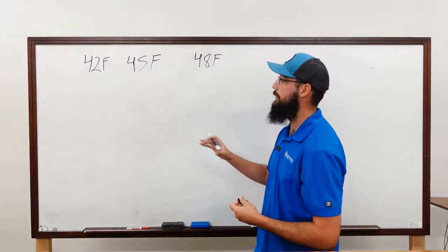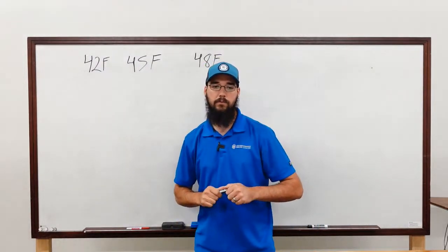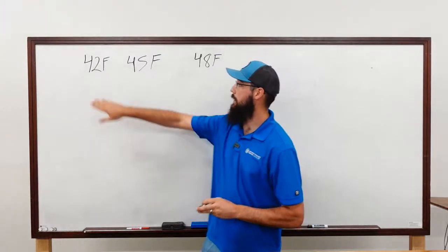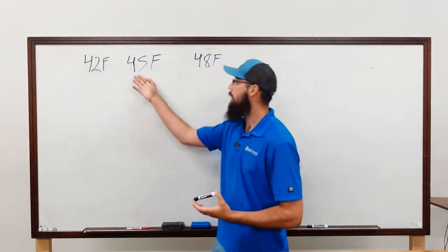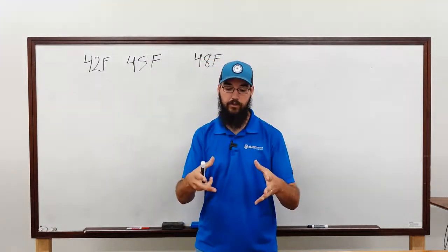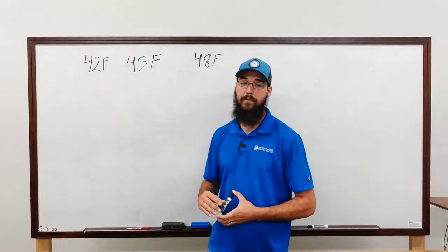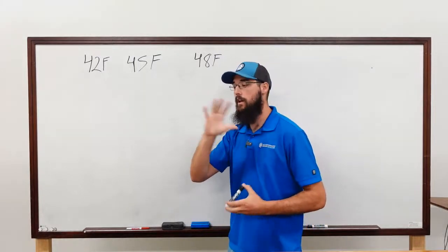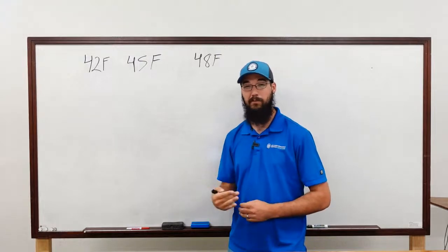And there's a lot of buildings, and I'm seeing this more and more. I'm not exactly sure why, to be honest, but for whatever reason, a lot of the engineering firms are speccing 42 degree systems more than I've seen them do in the past. Usually, 44, 45 on the chill water coils and the chill water loop and even the chiller spec itself was the most common on a lot of older equipment. And 42 is now becoming a lot more common. Again, I'm not sure why. If anybody has any input on that, throw it in the comments. I'd love to hear some perspective on that.